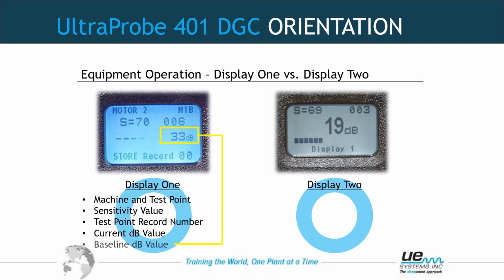Then we have the baseline indicator. If the Ultraprobe 401 grease caddy instrument setup is set to automatic and not manual, the baseline information from the route, from the DMS software, will be transferred back to the 401 grease caddy. So here we see the baseline reading for this particular reading, record number 6, motor 2, motor inboard bearing, was 33 decibels. Once I have a decibel here, I can compare the current reading to the baseline reading.